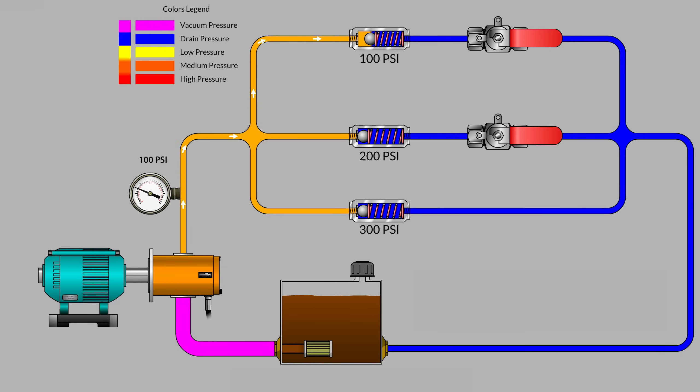Now let's bring up our control panel so that we can operate our shutoff valves and I'm going to close the top valve. What do you believe will happen to our system pressure when we close the top valve? 200 psi becomes our new system pressure because the middle branch is our new path of least resistance.